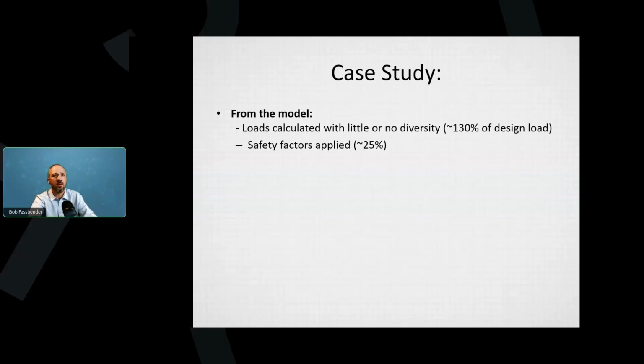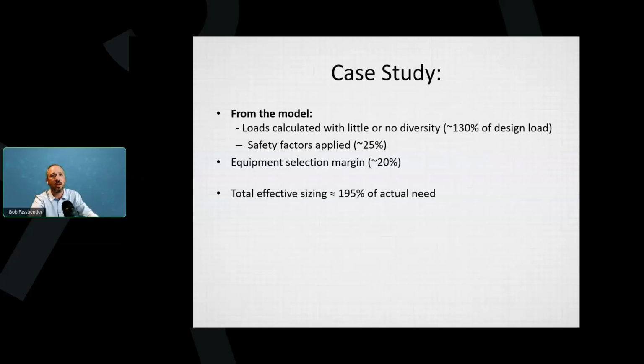So there's a building. They made the energy model and they used loads with no diversity, as we said. So they're at 130%. Then they add their 25% safety factor. And then, of course, when they get to the equipment, you pick your equipment and they upsize it by a margin of 20%. So if you add those up, it's not quite as big, but if you multiply them, we're at 195%. Anyone who's been in the field knows that everything tends to be oversized. So it's surprisingly common, and don't worry, it gets much worse.